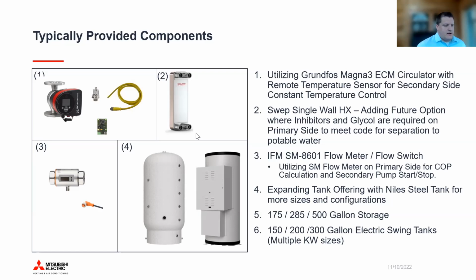There are some different controls, but one of the other main things is the tanks. If you look at any of the storage tanks in the marketplace today, there are very few that actually meet the needs of this type of single pass heat pump system. We're going to have a couple different offerings for this. Today we have one, but the biggest key is that on the inlets and outlets of the tanks, there's a baffling or sparge system to reduce the velocity in and out of the tank. It also turns the direction of flow. Instead of having flow coming right down into the tank and mixing, it turns that flow 90 degrees and slows it down so you get the best stratification out of the tank.